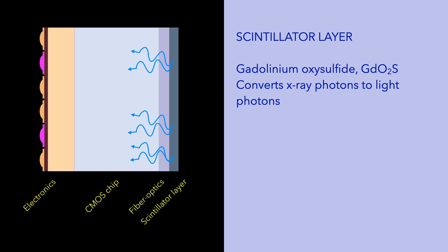Using a scintillation layer, we increase the efficiency of conversion of X-ray photons to signal. The fiber optic plate minimizes diffusion of the light photons that are produced at the scintillation layer and enhances the image resolution.